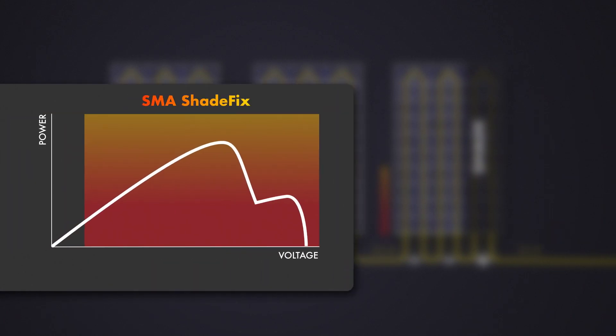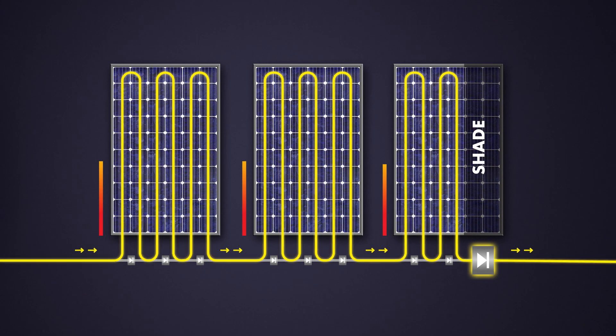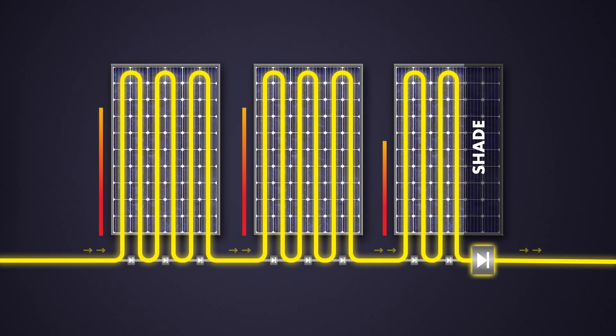Let's see what happens to the partially shaded PV array using SMA ShadeFix. The inverter will recognize the higher global maximum powerpoint at a lower voltage and will set its operating point accordingly. Due to the technical properties of PV modules, this will force the bypass diodes of the shaded PV module into conduction. There's no communication needed. SMA ShadeFix forces the bypass diodes to bypass the shaded PV module. All the PV modules, except the shaded ones, produce full power.